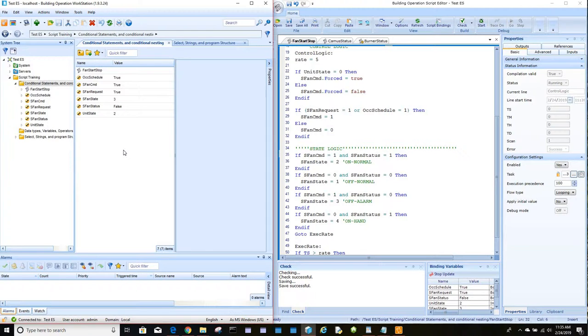You just have to make sure that you add some underlying logic so that when you are going to force a point into place in the I/O module on an ASP, you set the state to the state that you want it to be latched on before you execute logic that makes use of this binding forced attribute.